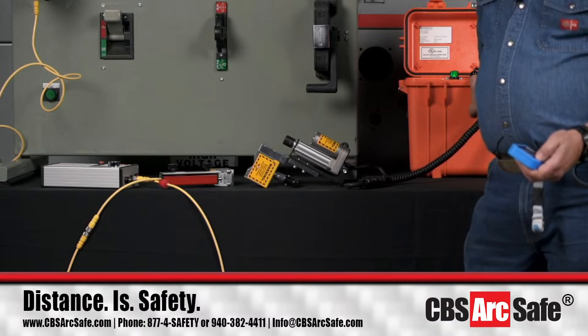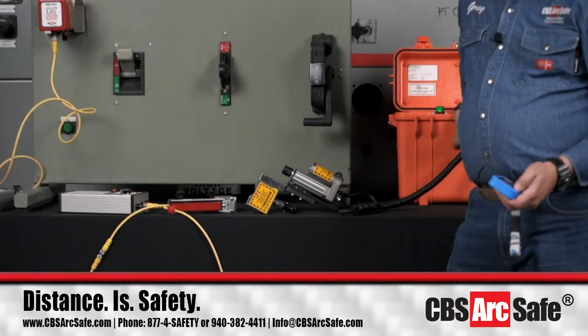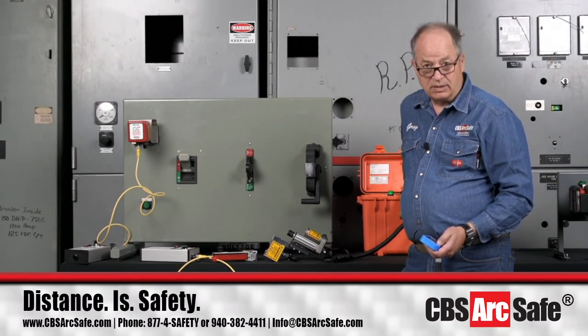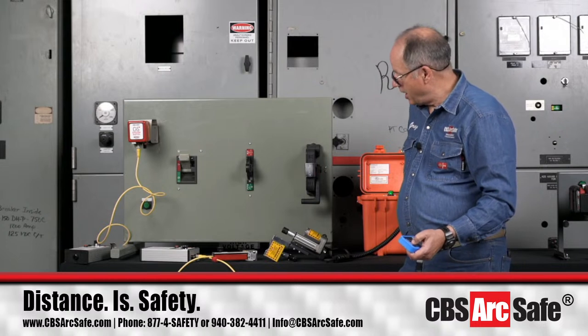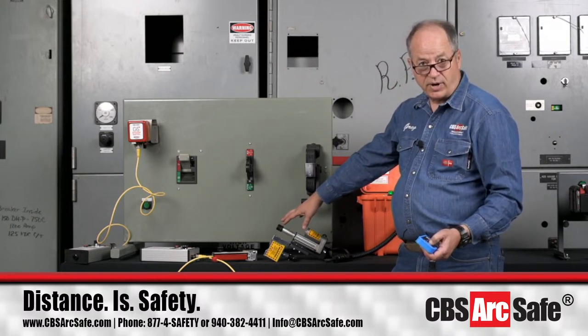So there are different circuit breakers that when we set up AR functionality on a remote switch actuator, it's based upon the circuit breaker and what we need it to do. So I need to be able to just close this. I don't want that to stay out there extended like this. I want it, as soon as I hear the breaker trip, to be able to release it and have it come back.